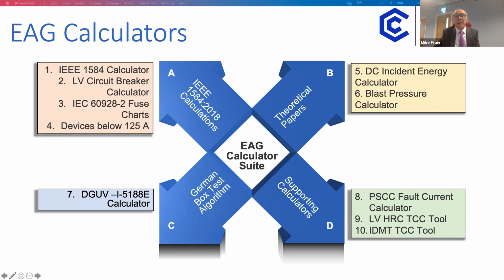So, on to the next one: theoretical papers. For DC incident energy, we've got a calculator for that. It's not in the same mold as IEEE 1584, but is based on theoretical peer-reviewed papers, as is blast pressure. In the bottom left corner there's also the German box test algorithm, from Europe, based on the testing of PPE to what we call the box test, and out of that an algorithm has been created based on theory, which is also included.